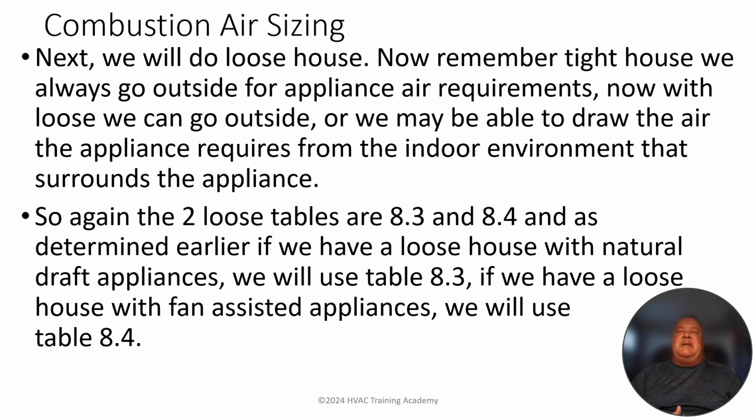But of course, now as we tighten up that house to make it more airtight and more energy efficient, we're not going to be able to get the air for these appliances near as easily. So we have to take this into account. The loose tables give us the option of saying, okay, we don't necessarily have to have holes cut in the side of your house, bringing air in from the outside into the appliance area. In this case, we might have enough air inside the house to satisfy the requirements of those appliances. So the first option we have in loose is to calculate whether or not we have enough air in the house to support the combustion of the appliances that we're talking about.